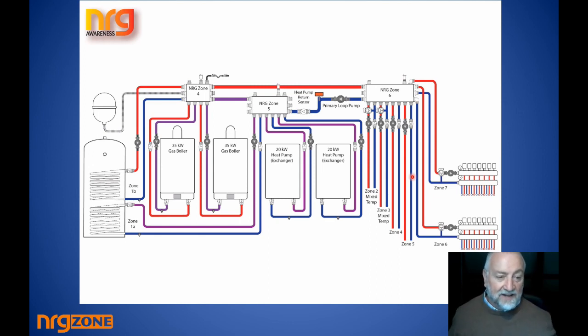We've got every attribute that a proper system should have with regard to energy efficiency, with regard to safety, with regard to neutral point creation. Again, our pressure vessel could be introduced here. I would suggest that's a good idea. It could also just as easily be introduced here, because that pipe is connected by an open path directly to here. I would think this is probably the best place. The cold feed could be brought in here. It could even be brought here. Where I'm showing it is brought in up here.